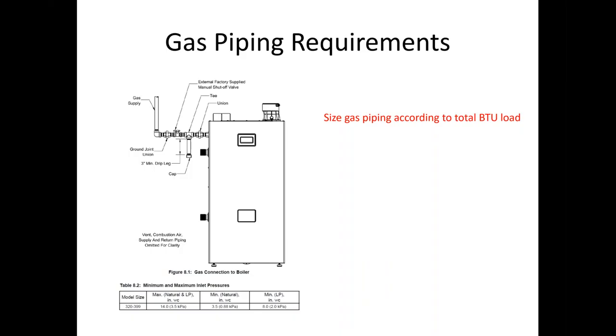Another thing with CSST: if we bring the CSST right to the products with no straight pipe, when they're in their higher firing ranges, we can get some whistling. Again, the negative pressure gas valves are going to draw in the gas as fast as possible, and you will get a harmonic sound out of the CSST.